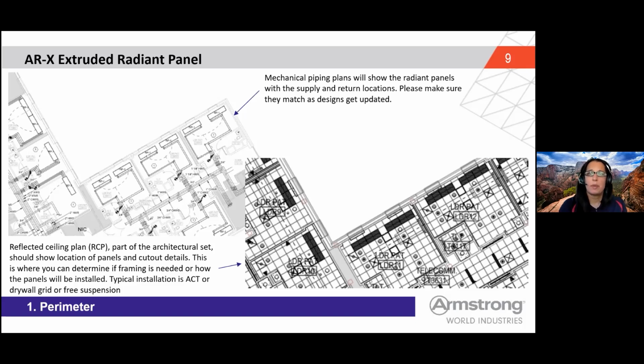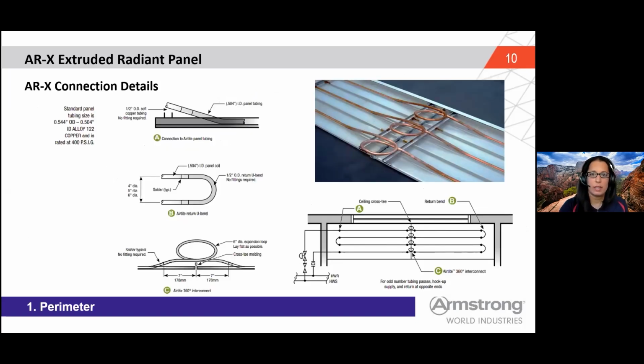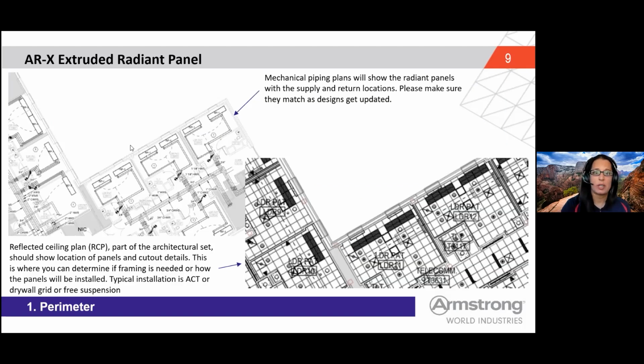The mechanical piping plans, sorry about that. The mechanical piping plans, which is up here in the corner, this will show where the radiant panels are. They should match, obviously, the RCP. And it shows the supply and return locations. You don't need to figure this out all on your own up front. We can help with zoning and really kind of feeding the different tubes, but we need to know where the mains are, need to understand how much is required to get to the panels and how many kind of are together.